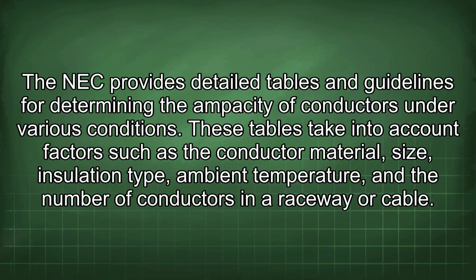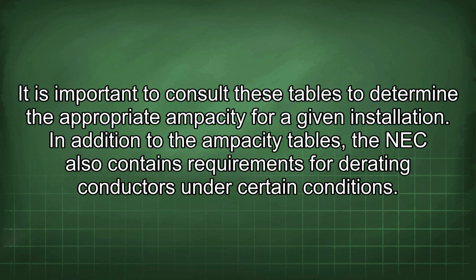The NEC provides detailed tables and guidelines for determining the ampacity of conductors under various conditions. These tables take into account factors such as the conductor material, size, insulation type, ambient temperature, and the number of conductors in a raceway or cable. It is important to consult these tables to determine the appropriate ampacity for a given installation.